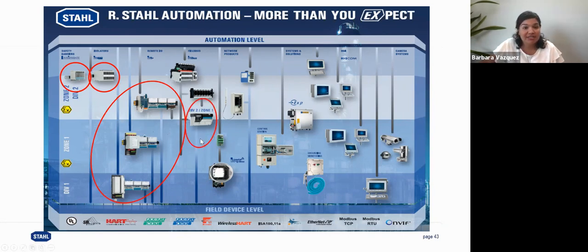Foundation Fieldbus intrinsically safe concept, that's FISCO. We have products for that. Ethernet connection, network connections in hazardous areas. We do have products for that. Our HMIs, believe it or not, some of them will have intrinsically safe circuits on their displays, as well as our ground monitoring will use some intrinsic safety circuits to achieve the Class 1 Div. 1 installation.